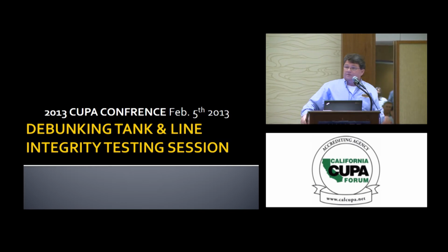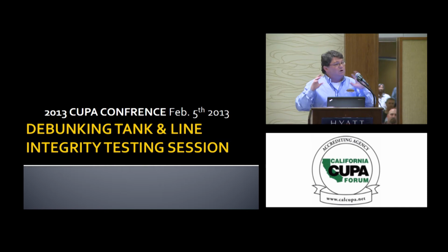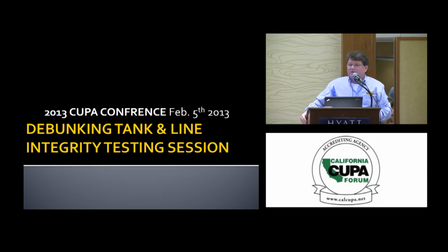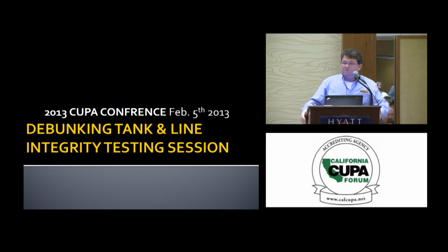Troubleshooting. What does that mean? My Veeder-Root is periodically showing me a fail, or something's happened periodically. That's when you need tank testing. That's when you need somebody that knows the science of tank testing, that knows how to troubleshoot. Let me ask you, if you think you have a little bit of a release or a leak problem, and Brad and I went out to do the test, and Brad sucked on one end of the vent, and I sucked on the other end of the tank, and we found the leak, would you ask us, was that certified? You'd say, thanks for finding the leak. Troubleshooting doesn't mean anything to do with compliance. Zero. Find my problem. Tank testing has to change when they go to troubleshooting.